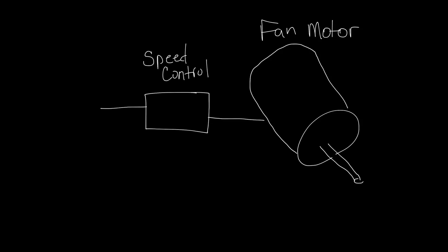Generally speaking, fan-powered terminal units require a speed controller in order to make the necessary balancing adjustments to match the fan airflow delivery to scheduled air volumes. This adjustment is typically made by the balancing contractor, and it's necessary in order to compensate for external pressure and operating conditions in order to deliver design airflow from a blower.